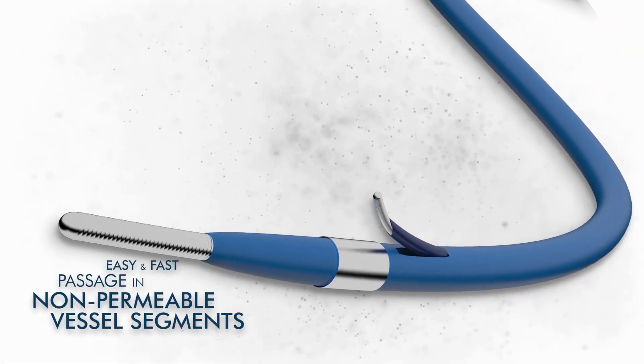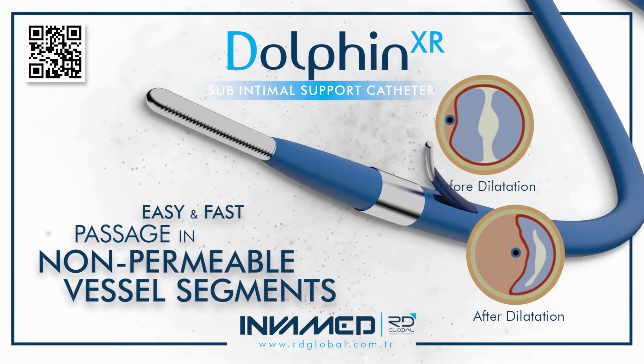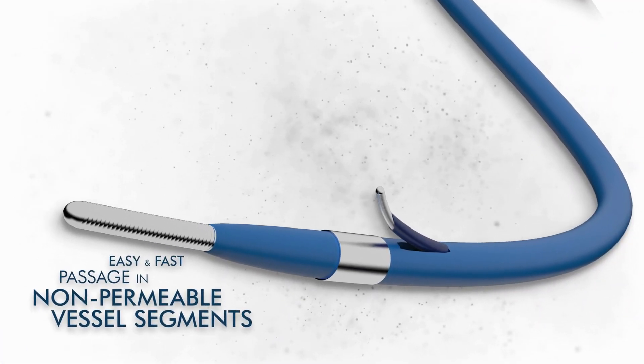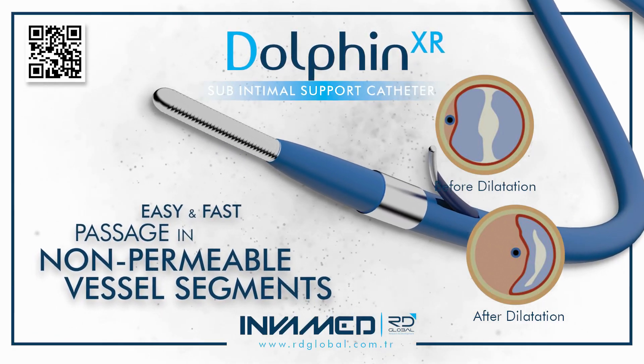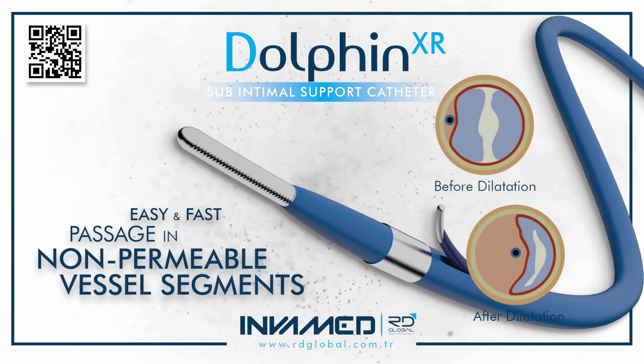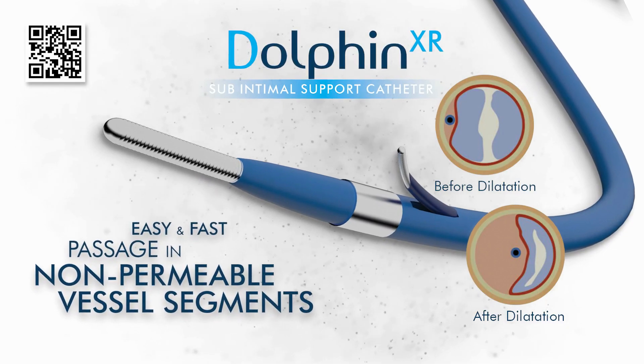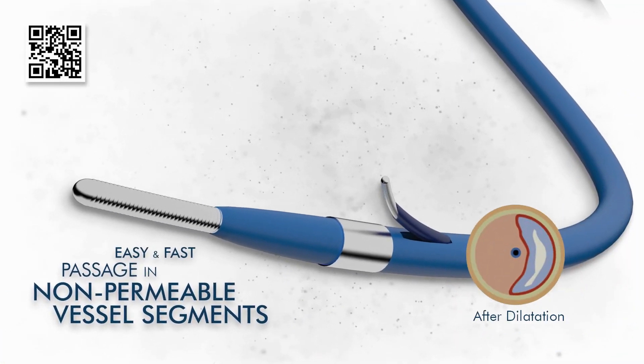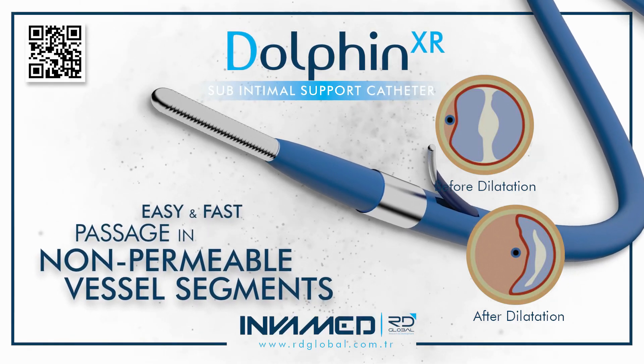From a design standpoint, Dolphin XR is built for deliverability. Its shaft features a balance of flexibility and longitudinal stiffness, ensuring forward motion without prolapse, even through tortuous vessels. The balloon's short cone transitions and compliance gradient allow it to conform to vessel geometry while minimizing dog-boning or edge dissection risks. During inflation, operators maintain control with pressure feedback systems, ensuring vessel expansion is both predictable and safe. The catheter's radiopaque markers enhance procedural accuracy, guiding placement and confirming full lesion coverage. After deflation, the balloon's rapid refolding allows quick withdrawal and repositioning for multi-zone treatments.